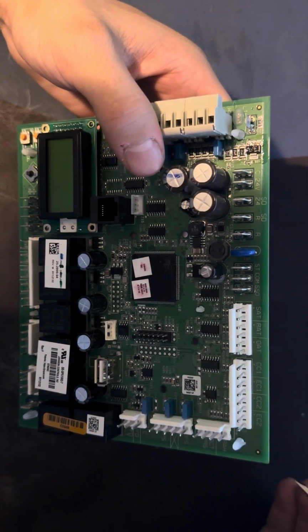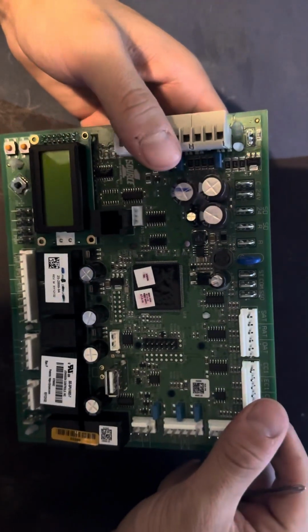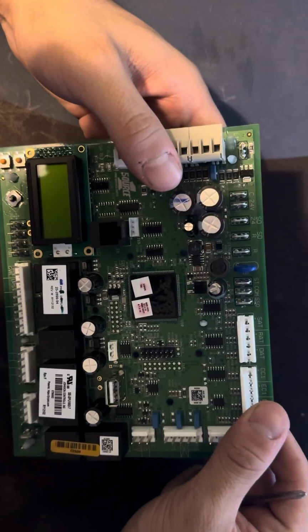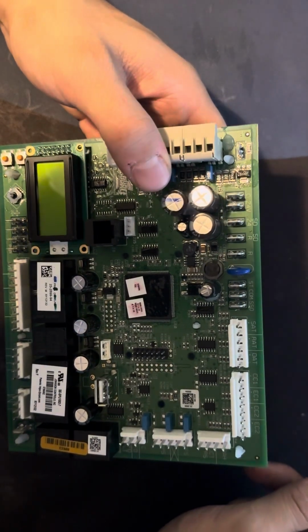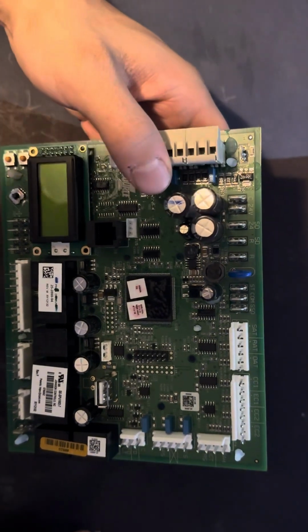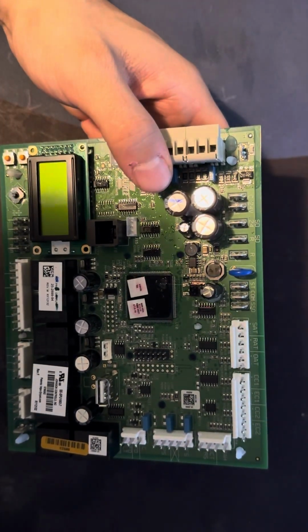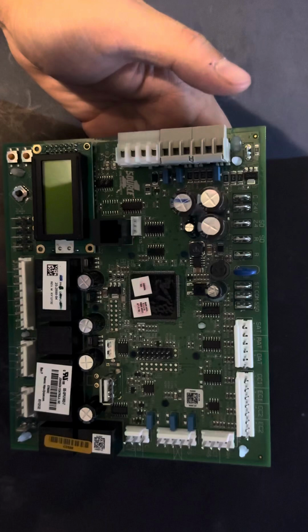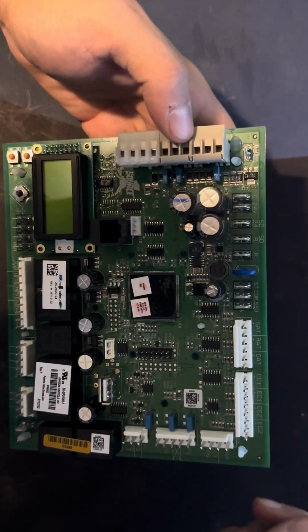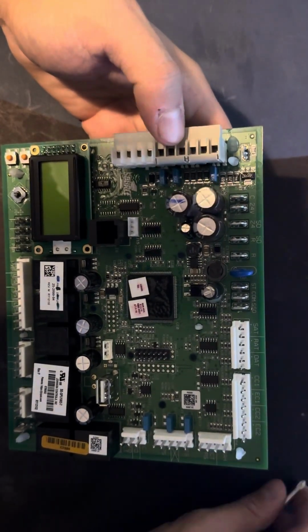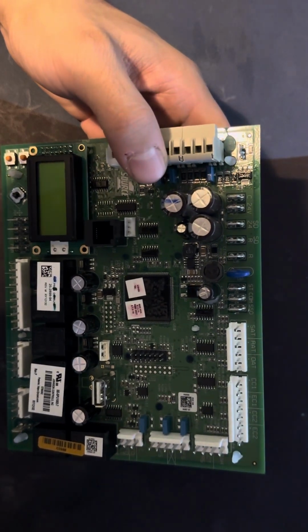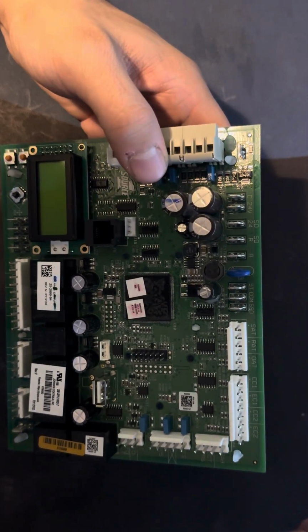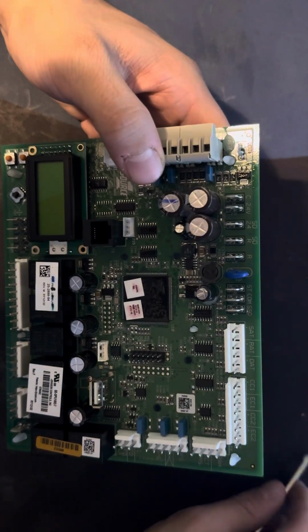Okay, now this board is constantly monitoring the limit circuit. When I'm talking limit circuit, I'm talking about the heating limit circuit, which includes only the primary limit switch and the auxiliary limit switch. It does not include the rollout. It's constantly monitoring that limit circuit, even if it's idle, always. Cooling, heating, idle, whatever it's doing.